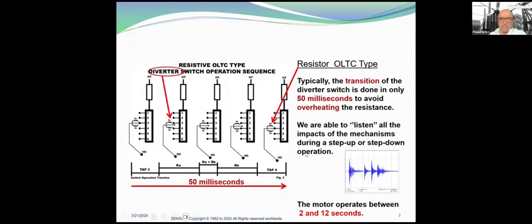Here you have a typical resistor OLTC type, and you can see the diverter switch operation sequence. Typically, the transition of the diverter switch is done in only 50 milliseconds to avoid overheating the resistance. We are able to listen to all the impacts of the mechanism during a step-up or step-down operation. The motor operates between 2 and 12 seconds. In these graphics, we are moving from tap 3 to tap 4, and it shows exactly how the resistances are connected during this transition.